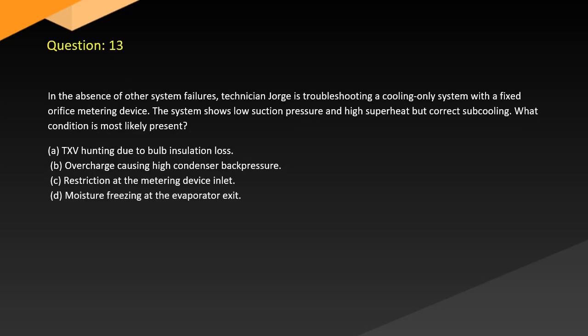Question 13. In the absence of other system failures, technician Jorge is troubleshooting a cooling-only system with a fixed orifice metering device. The system shows low suction pressure and high superheat but correct subcooling. What condition is most likely present?